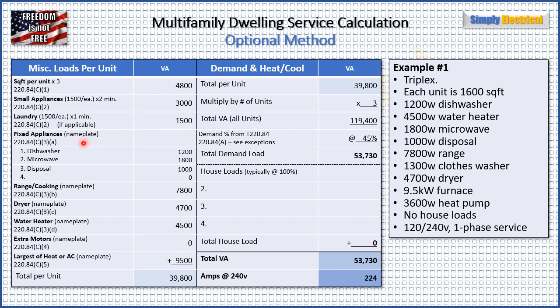Then we go to fixed appliances: dishwasher, microwave, and disposal with their listed values. We have a range — nameplate 7,800 watts. Dryer at nameplate 4,700 watts. Water heater at nameplate 4,500 watts. No extra motors. For heating and cooling, we have a 9.5 kW furnace and a 3,600 watt heat pump — so we take the furnace at 9,500 watts. Totaling the column, we get 39,800 VA per unit. We slide that number up and multiply by 3 units, giving us 119,400 VA total.